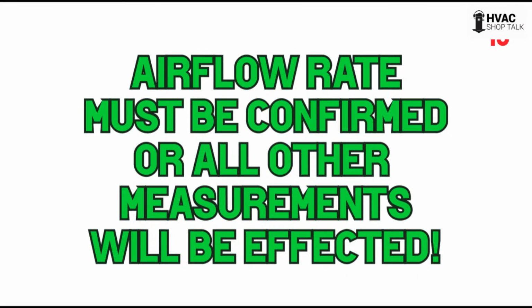Airflow rate must be confirmed or all other measurements will be affected. It's the same premise. If you don't confirm the airflow, later on we do calculations of total capacity. It's not going to work. Every step has to be taken care of to reduce the chance of error. Is there going to be error? Heck yeah, there's going to be error. We're human beings. It doesn't even matter. If we were cyborgs, we still have a bunch of test instruments that have tolerances, plus 5%, minus 5%. You make 10 measurements with things that have a 5% tolerance. That all adds up to a much larger error. So try to keep it tight as you can, but you're not going to make it perfect.